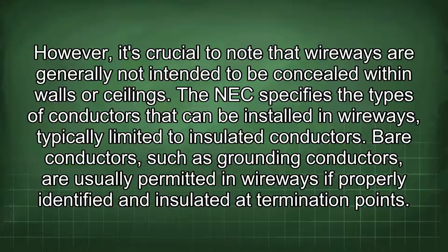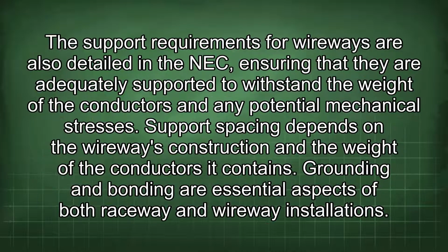However, it's crucial to note that wireways are generally not intended to be concealed within walls or ceilings. The NEC specifies the types of conductors that can be installed in wireways, typically limited to insulated conductors. Bare conductors, such as grounding conductors, are usually permitted in wireways if properly identified and insulated at termination points. The support requirements for wireways are also detailed in the NEC, ensuring that they are adequately supported to withstand the weight of the conductors and any potential mechanical stresses. Support spacing depends on the wireway's construction and the weight of the conductors it contains.